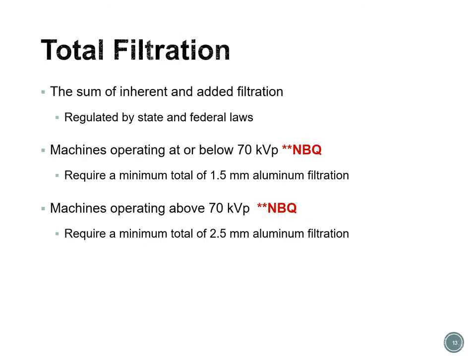Adding together inherent filtration and added filtration gives us what is called total filtration. Machines that operate at or below 70 kVp require a total of 1.5 millimeters of aluminum filtration. Machines operating above 70 kVp require a minimum total of 2.5 millimeters of aluminum filtration. Since inherent filtration is about 0.5 to 1 mm, we can calculate how many additional 0.5 mm aluminum discs are needed to reach the required total for machines above or below 70 kVp.